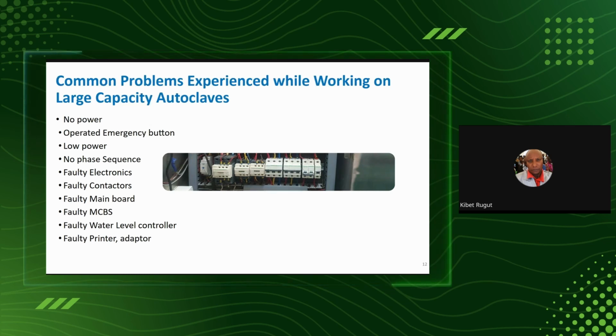So common problems, just a general overview of what you come across in an autoclave, and you may or may not have them in your technical manual, maintenance manual. There could be power failure. Maybe someone has falsely operated the power emergency button. The autoclave may be getting voltages which are below the ratings, or the wrong phase sequence, so the electronics can also be faulty. If you have so many power blackouts or ups and downs, which we call surges, the contactors, because of their making and breaking many times in a cycle, could have arcing, and that makes the transmission of current weaker than it should be.